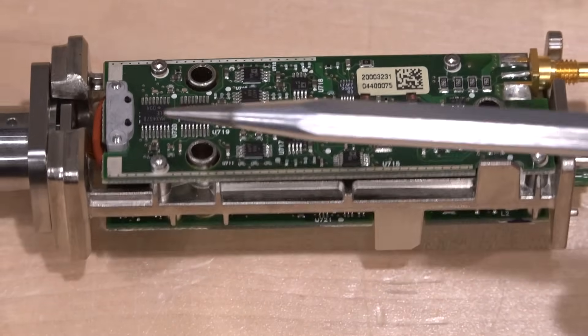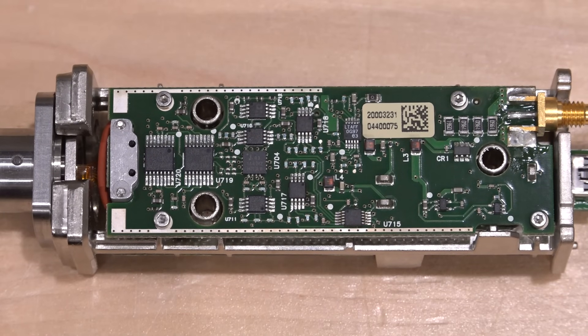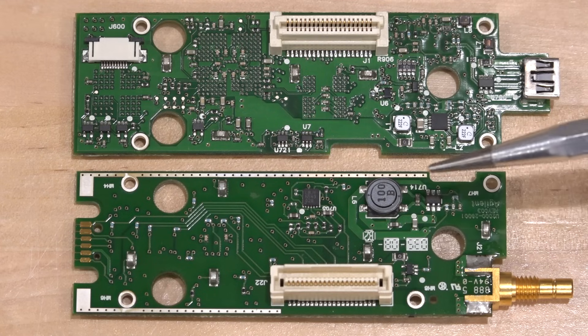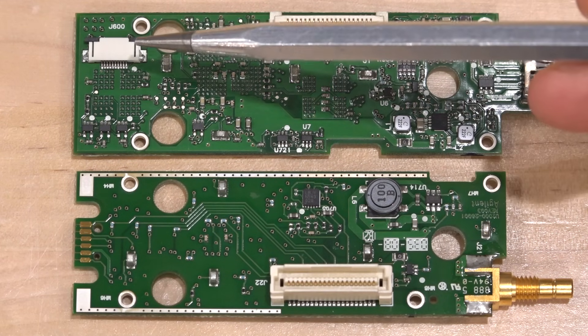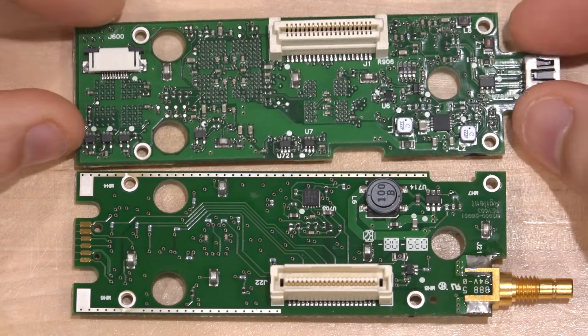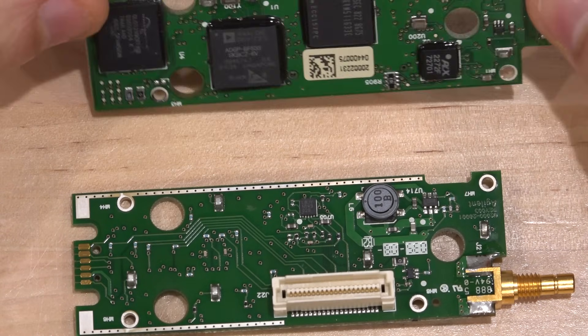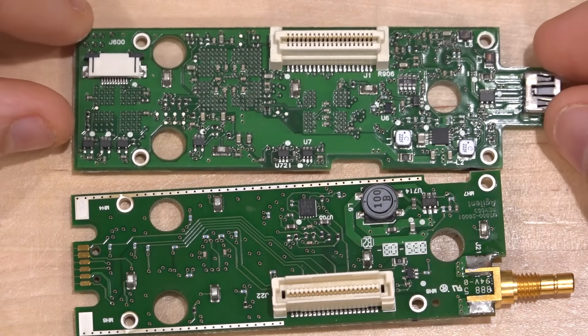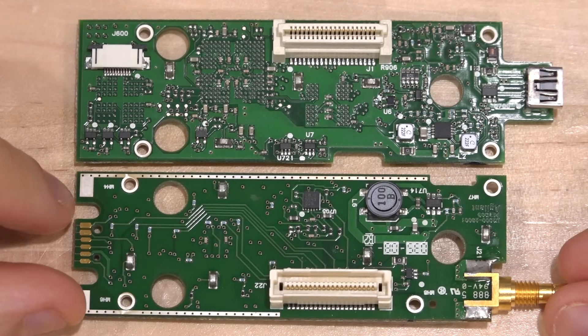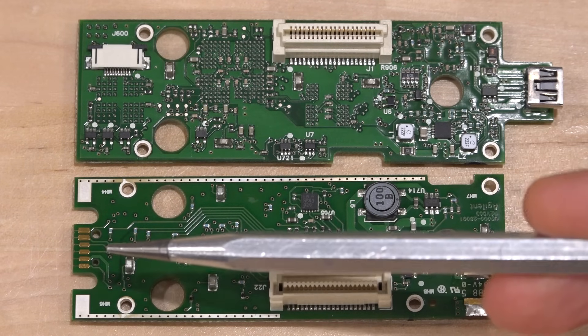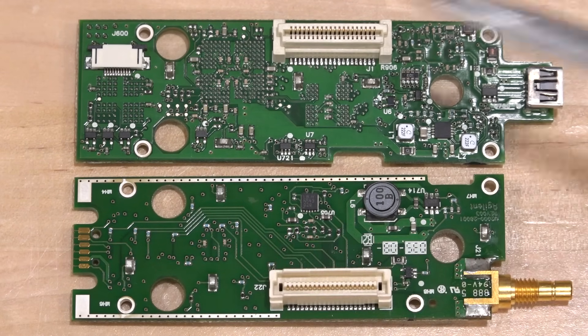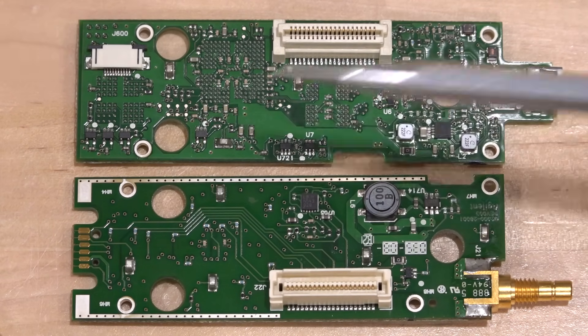Here's the other side of the two boards. There's not much going on, just some inductors, potentially some DC-DC conversion. But there is a ribbon cable attachment point here sitting exactly on the other side of the flash memory. This is probably how the information is downloaded into the memory and potentially how it's calibrated when it's opened up. These exposed pads are where the sensor directly plugs in. This assembly is done completely separately from each other, allowing you to replace these boards or the sensor if something goes wrong.